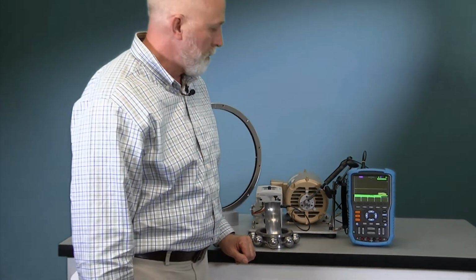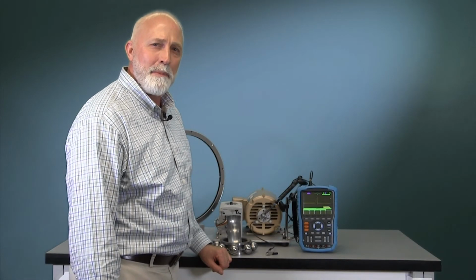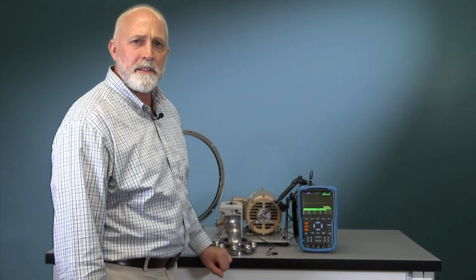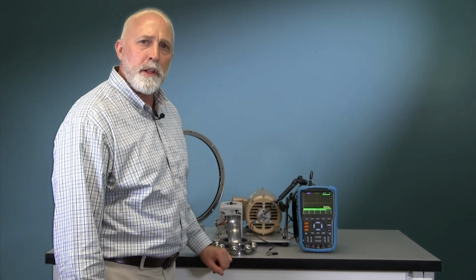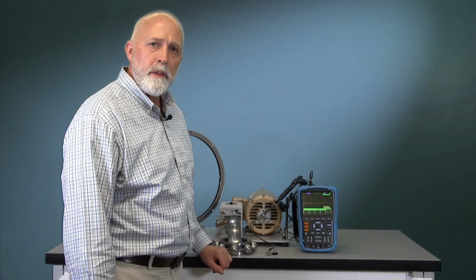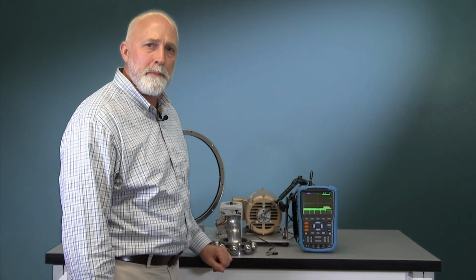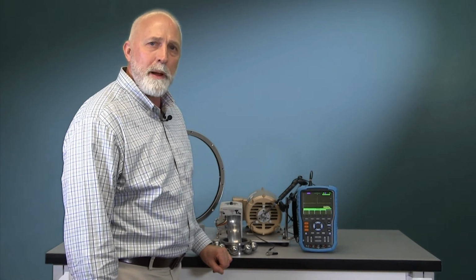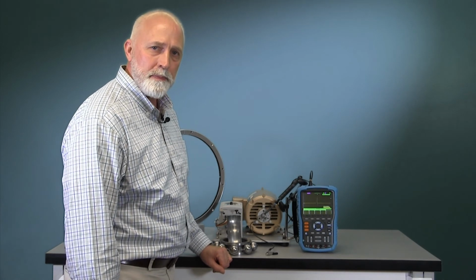voltage on a motor. So what you've seen here today is a motor operated by a VFD being tested for shaft voltages. And when you connect the shaft grounding ring, those voltages are diverted away from the bearings and directly to ground, thereby protecting the motor bearings from damage and failure.